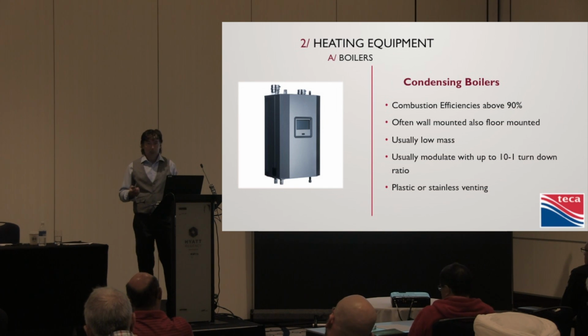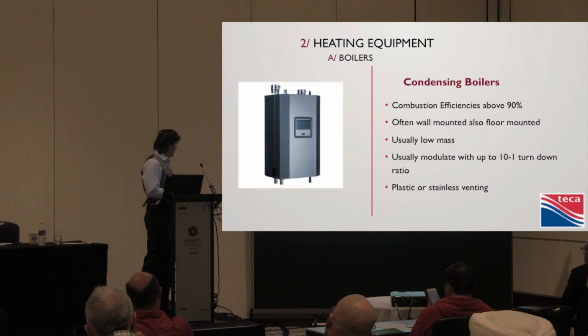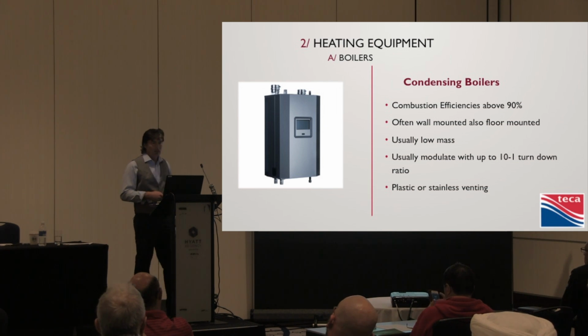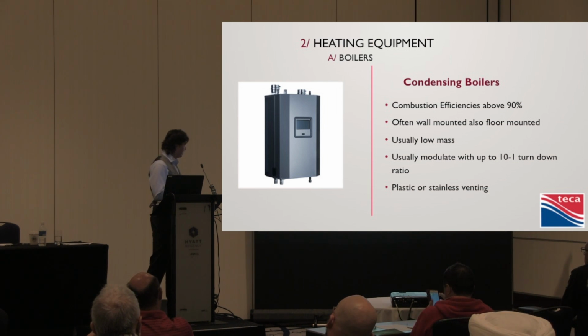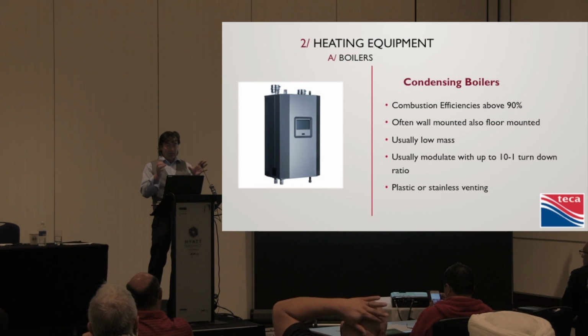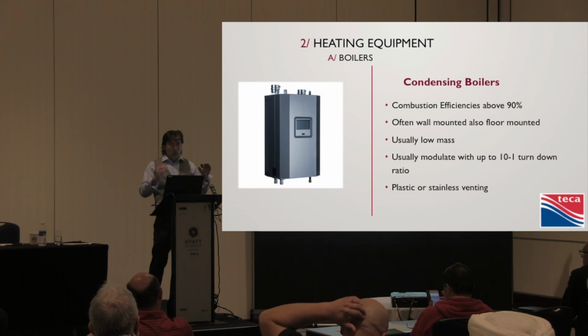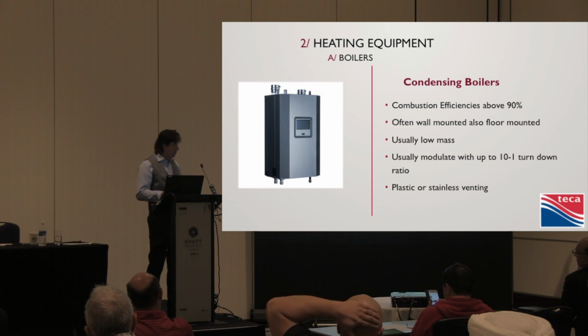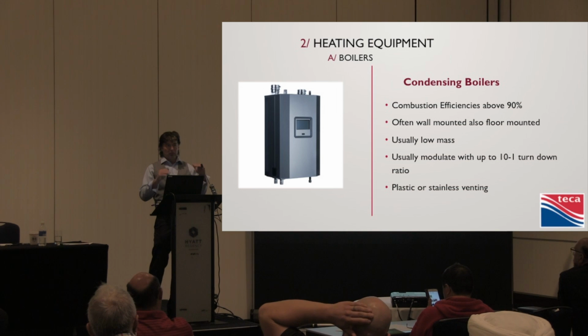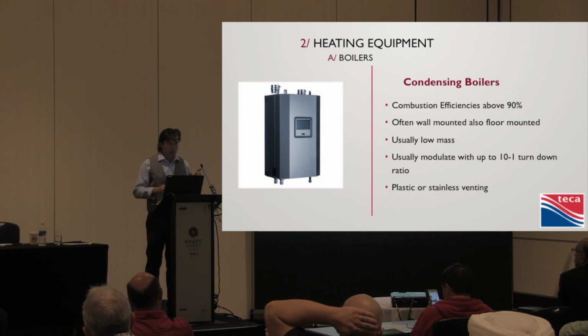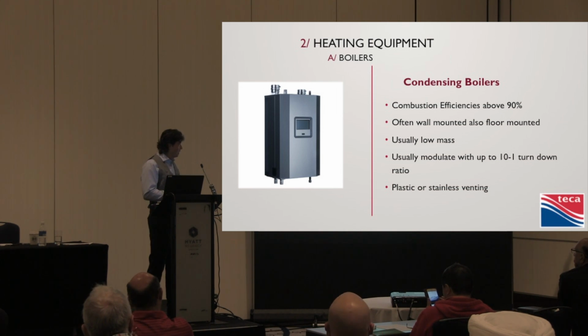So let's say you had one of these, and then you had another one of these. Let's say your load was 2 of these boilers, or you use smaller boilers. Now you'd have 2 boilers which can communicate. They will link together, and they will take turns, and they will also modulate their own burners to their most efficient level, so that now you take your 10-to-1 turn-down ratio and multiply it by 2 different boilers to hit the sweet spot of operation. So yeah, 90% or 95 or 96, that's great, but I like this part of things.